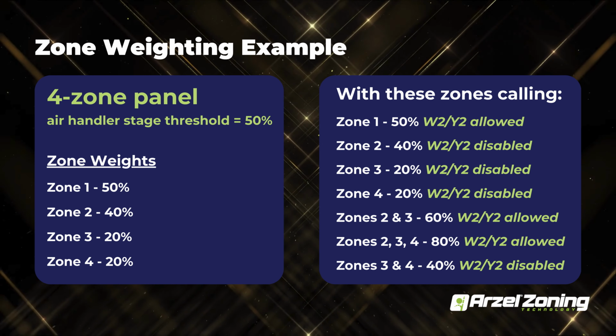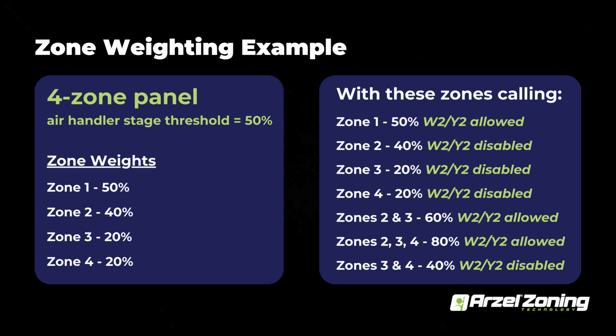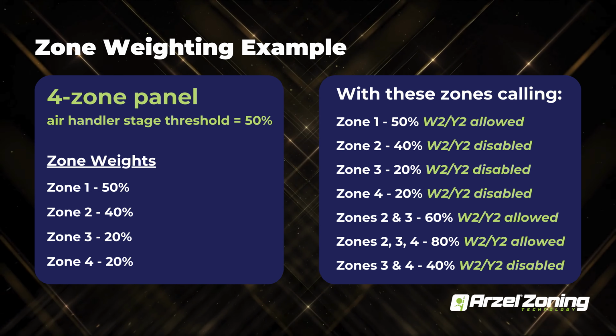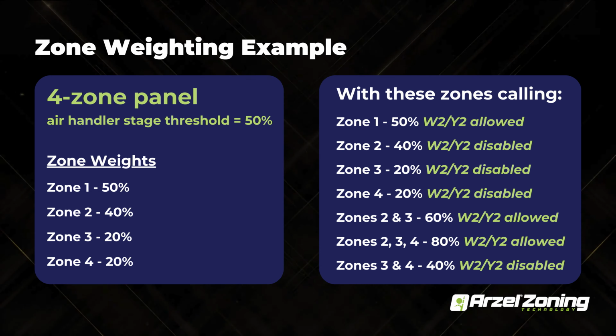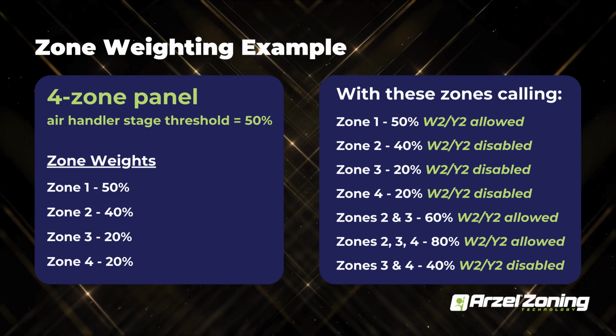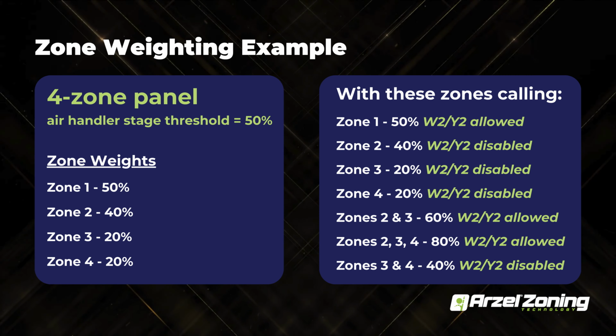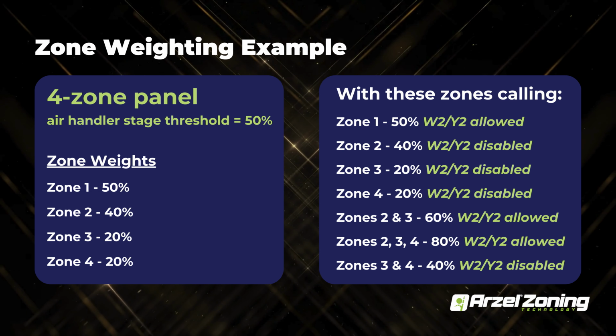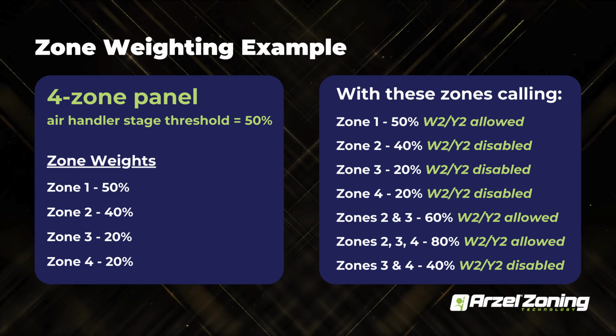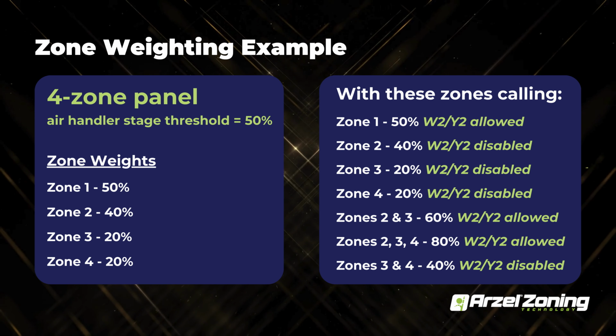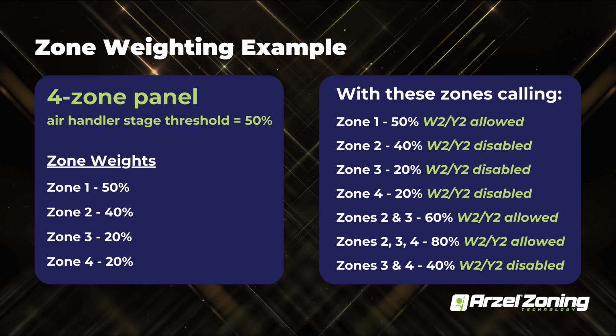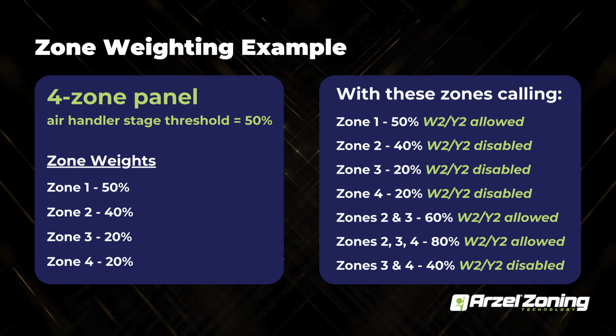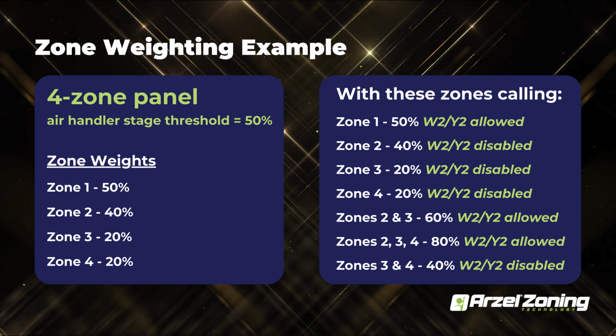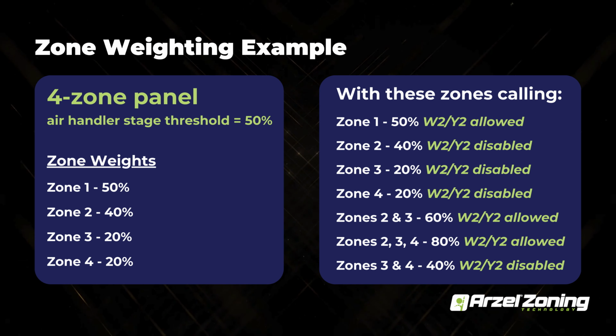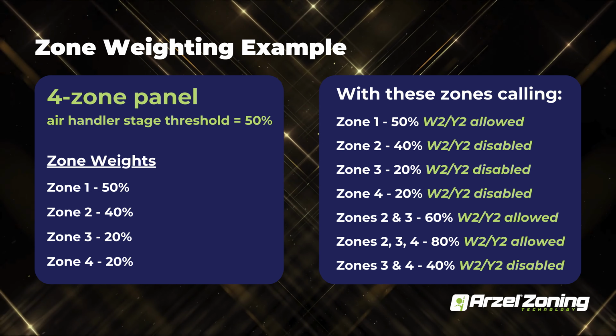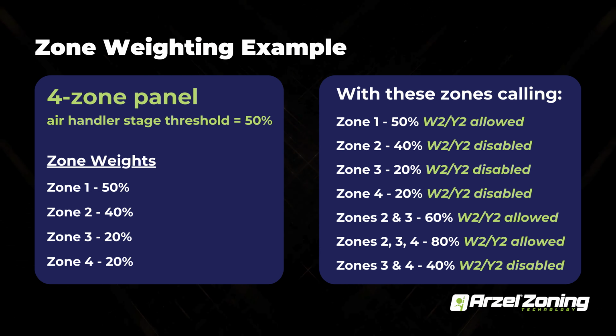The way that your zone weighting works is you're going to assign a percentage of ductwork per zone on your equipment. So say you have a 4-zone panel, you assign each of your zones: 50% for zone 1, 40% for zone 2, 20% for zone 3, and 20% for zone 4. And like I said, the zone weight plays off your air handler stage threshold. The way this actually works is if your zone weight is equal to or greater than your air handler stage threshold, it allows for second stage operation. If your zone weight is less than your air handler stage threshold, then it locks out second stage operation.